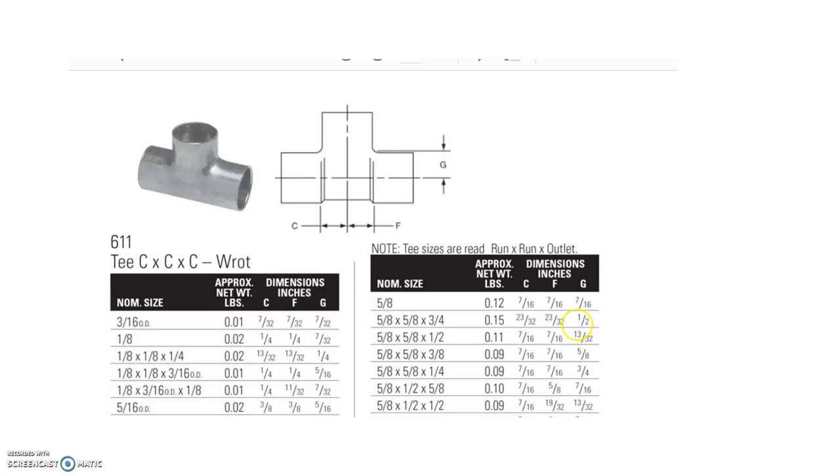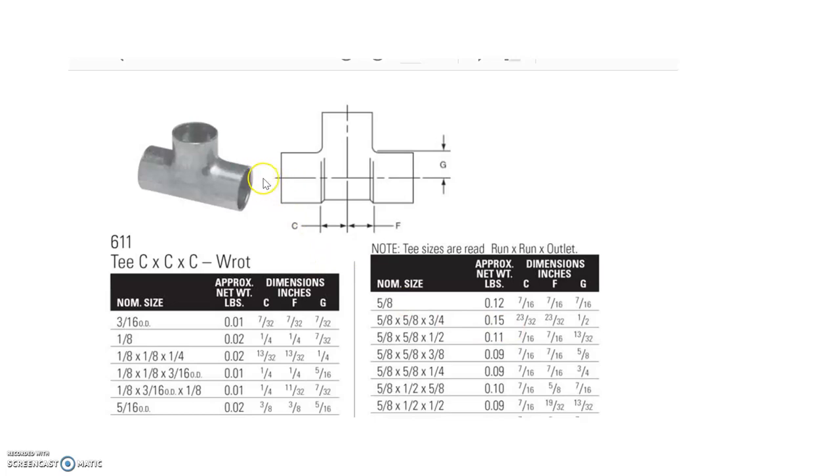So now to describe what the three sides are. First we have the 5/8" side. The 5/8" side refers to the C side, which is on the left-hand side here. It's always the bigger measurement in all three sides. It's one of the two sides that are opposite each other, so that would be the first side, and that refers to the C dimension. Again, that's the fitting allowance, 23/32".